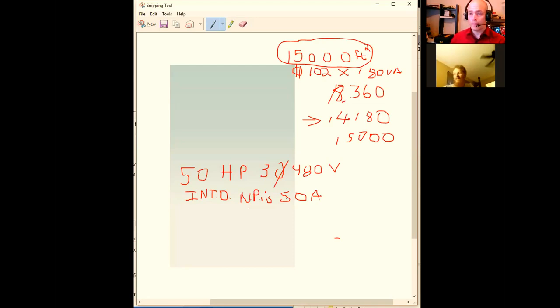Here's the deal though. The funny thing about motors, and I didn't really understand it as well until I got into the theoretical side of it, the teaching side of it. The nameplate's a hard thing to ignore. You pull a motor out of a crate, it's got a great big nameplate staring you right in the face. And with air conditioning equipment, we're required by code to take the manufacturer's maximum overcurrent protection, the MOP, on an HVAC or refrigerant motor as gospel. So even if your code calculation is higher, you still have to follow the manufacturer's ratings.